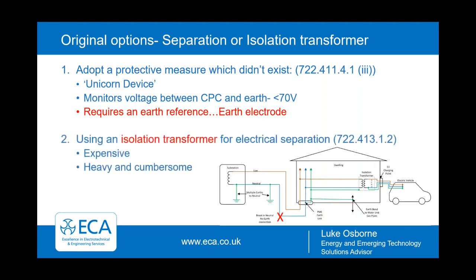There's also the option of using an isolation transformer for electrical separation. A great solution, but very expensive, heavy and cumbersome. And so there would need to be considerations as to where these would be mounted, as obviously it's additional in size and significant mass. And also there was the option of using a TT system, and there's potential issues behind that, which we will see now.